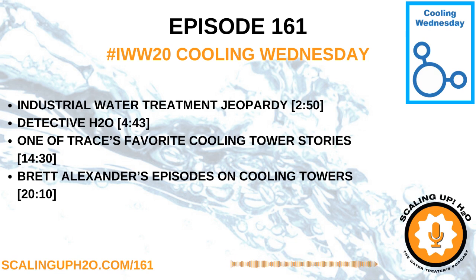A chiller ton is how many BTUs? What is 12,000 BTUs? A chiller ton is 12,000 BTUs, where a tower ton is 15,000 BTUs. They add an extra 3,000 BTUs for the parasitic heat that the chiller makes.